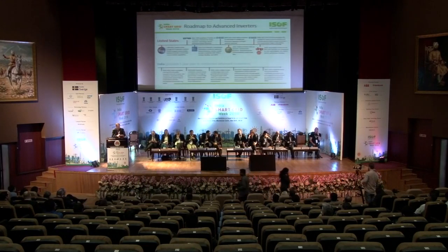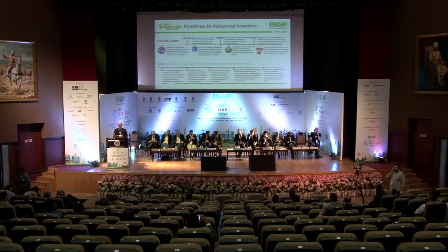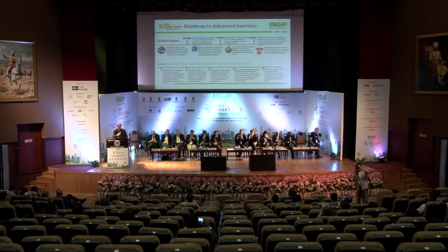I would like to present two parallel timelines here. The top one is what has happened in the United States and is currently happening, and the lower one is what I would propose India consider, leveraging some of the work that has gone on in Europe and the United States. Starting almost a decade ago, Sandia, EPRI, and others were researching these different advanced inverter capabilities, working with industry to add these functions and doing power systems testing with that. We've also done a number of simulations for all these different scenarios. Then, working with EPRI, we started adding these capabilities to both international and national standards.